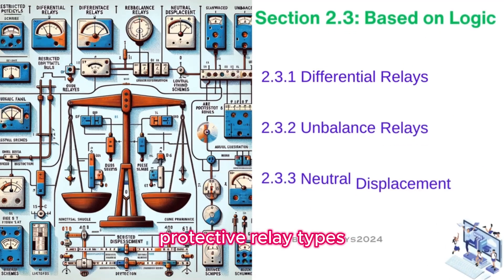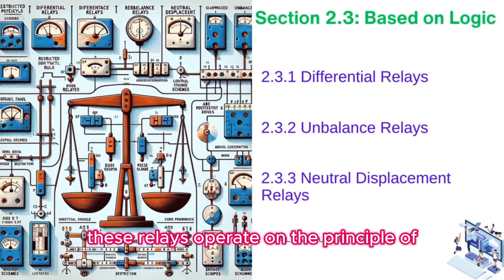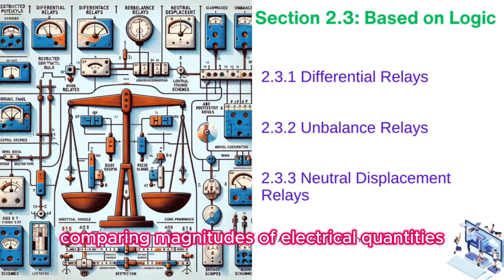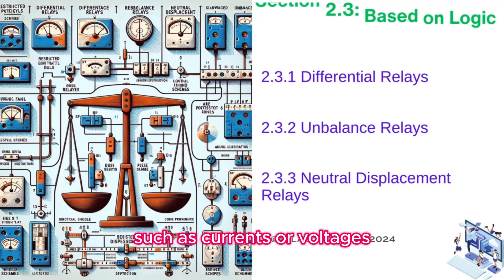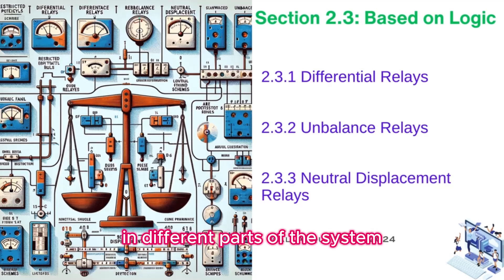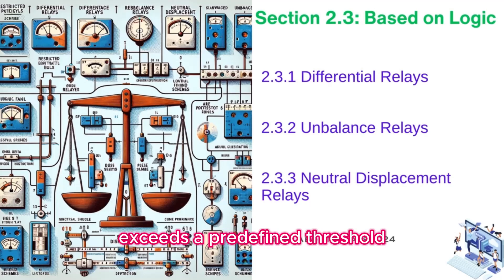Protective relay types based on logic. Differential relays operate on the principle of comparing magnitudes of electrical quantities, such as currents or voltages, in different parts of the system. A differential relay triggers when the difference between these quantities exceeds a predefined threshold, indicating a potential fault.